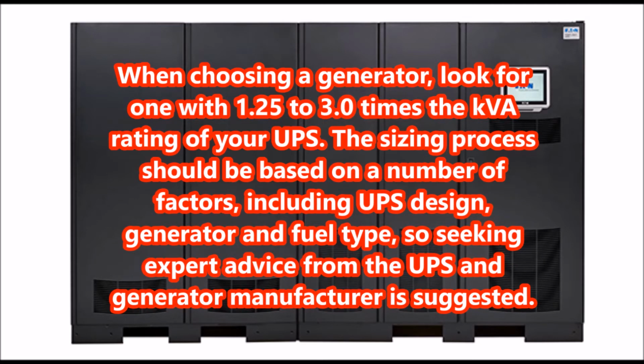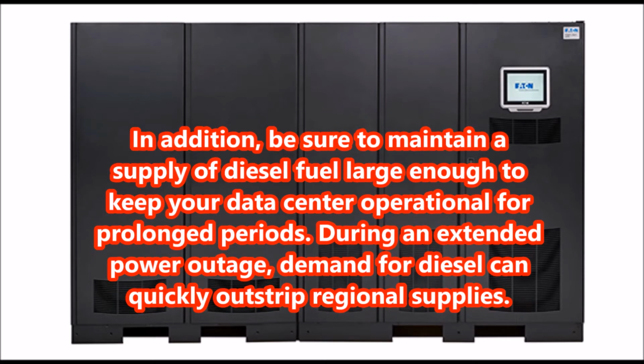When choosing a generator, look for one with 1.25 to 3.0 times the kVA rating of your UPS. The sizing process should be based on a number of factors, including UPS design, generator and fuel type, so seeking expert advice from the UPS and generator manufacturer is suggested. In addition, be sure to maintain a supply of diesel fuel large enough to keep your data center operational for prolonged periods. During an extended power outage, demand for diesel can quickly outstrip regional supplies.